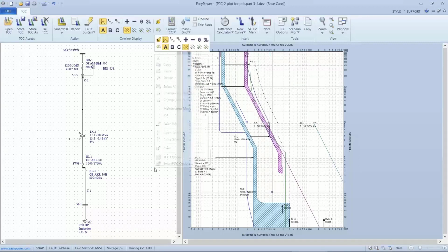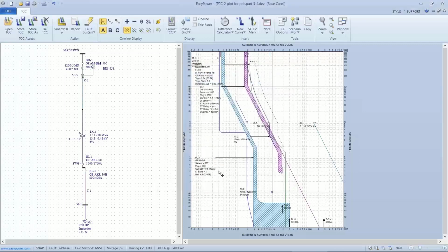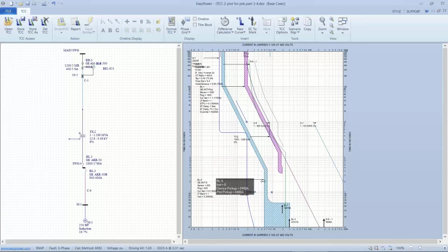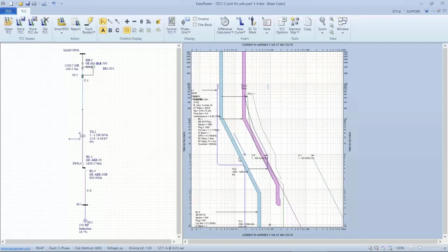First upstream device, we've got to set our first upstream device, which is BL3. BL3, it looks like it clears the asymmetric tail. I'm going to jog it just a bit to see if we can get a little better granularity. And there's a little bit of a concern about this being too close to the motor starting curve. I might adjust that, but we're well inside the thermal damage curve.